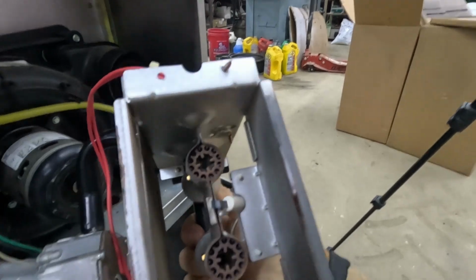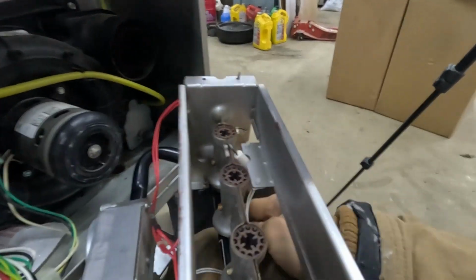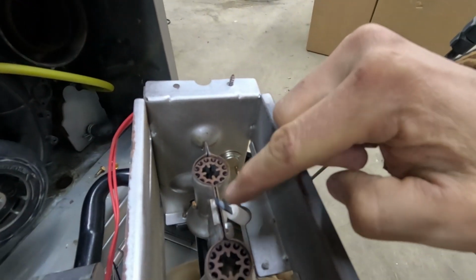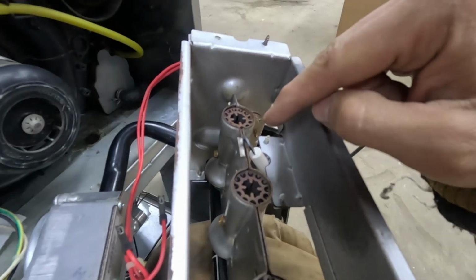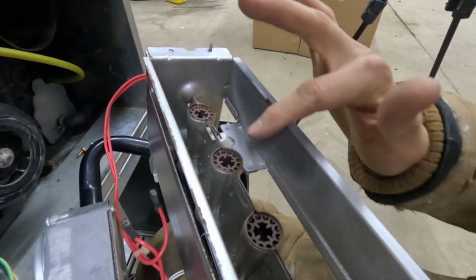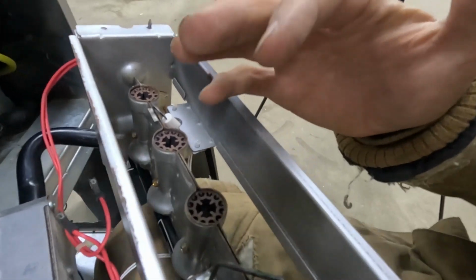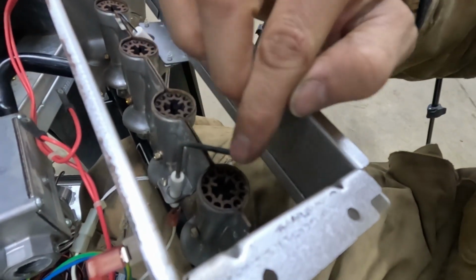And you want to be really careful to not bump or touch this. That's the igniter. They do tend to be pretty fragile. It's also a good time to inspect the burners. And while you have this out of here, it's also great to clean this flame sensor.